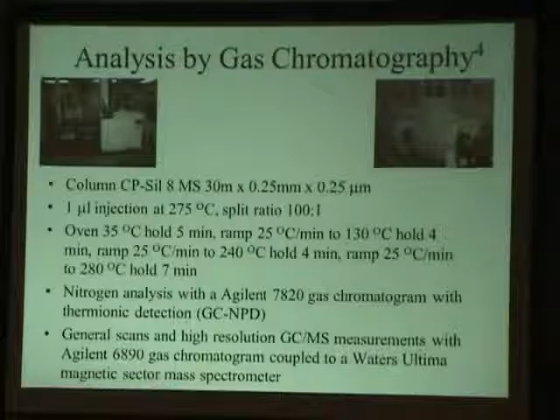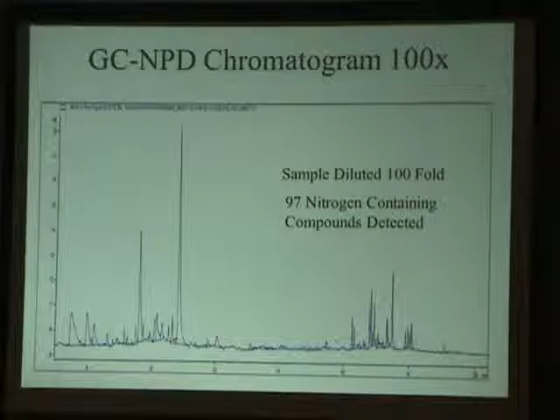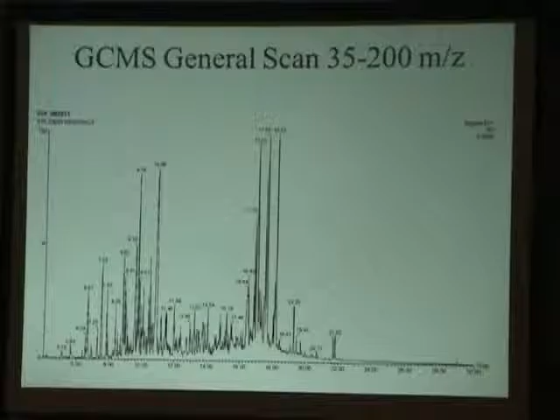This is a chromatogram of a 5-fold dilution of my extract, and I have 205 individual nitrogen compounds. That's a lot. It's a lot to deal with. So what I did is I just diluted it 100-fold, and now I got 97. So these are the 97 peaks that I'm going to focus on. The nitrogen detector will tell me where the nitrogen compounds are, and that's what I use that for. I use it like a guide. Then I run it by GCMS mass spec, and here's my general scan of the same sample. And you can see right here, this peak at 10.89 corresponds to this largest peak right here in the nitrogen chromatogram. All right, so that's the one I want to focus on first. I might as well start with the biggest peak.